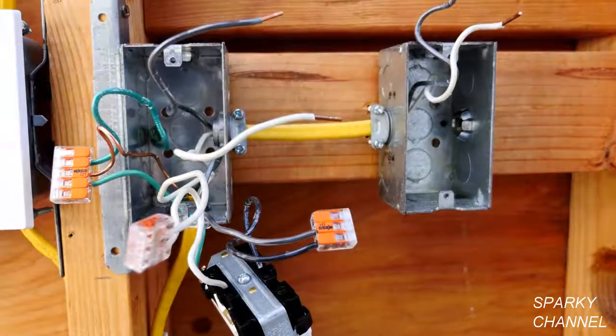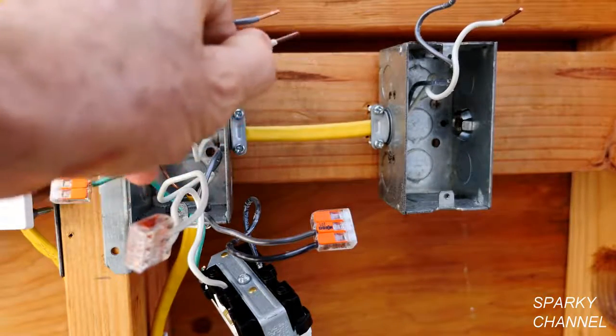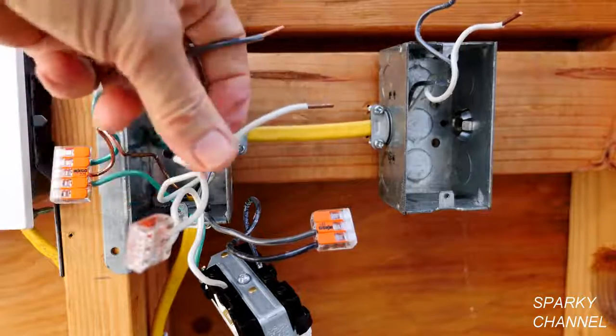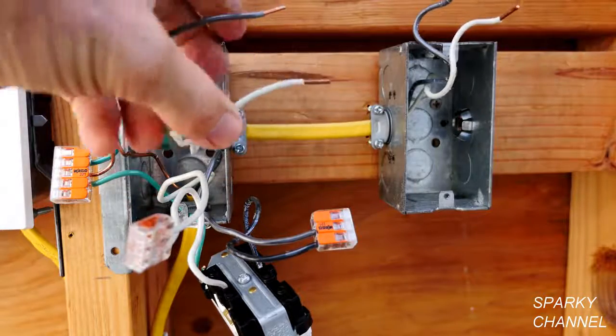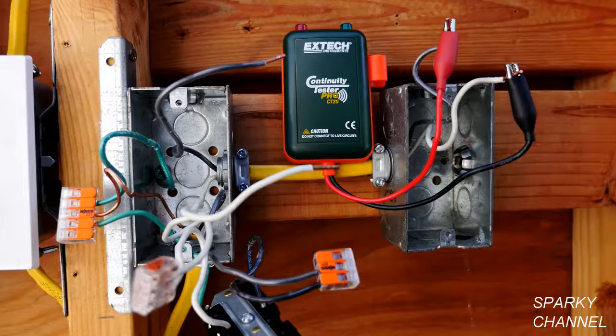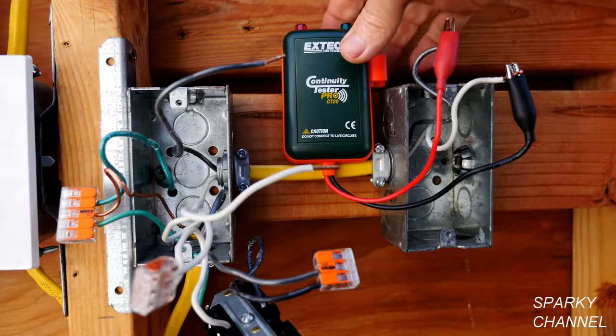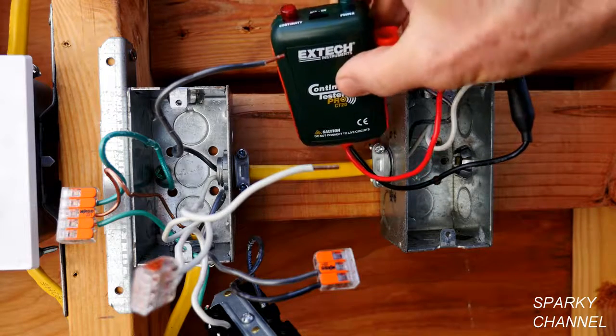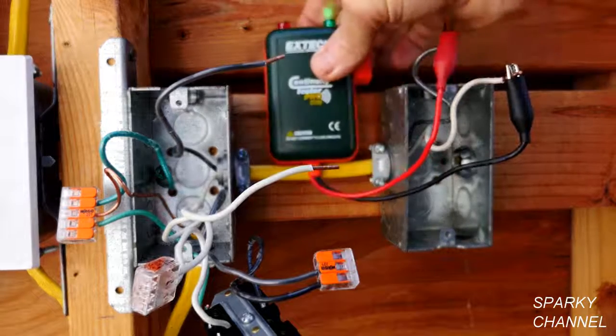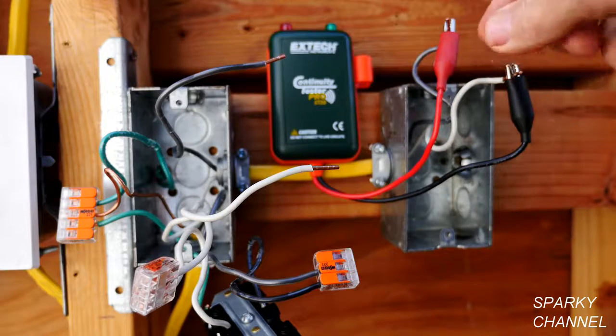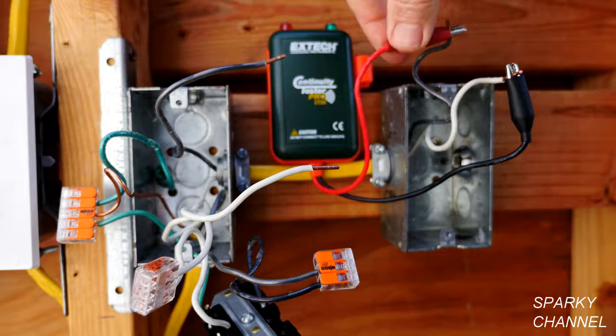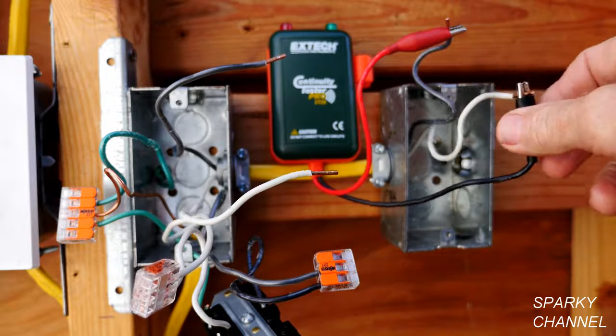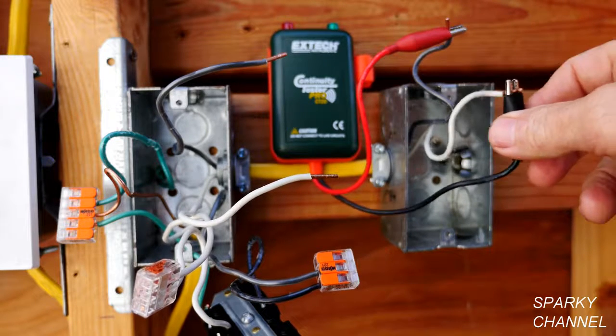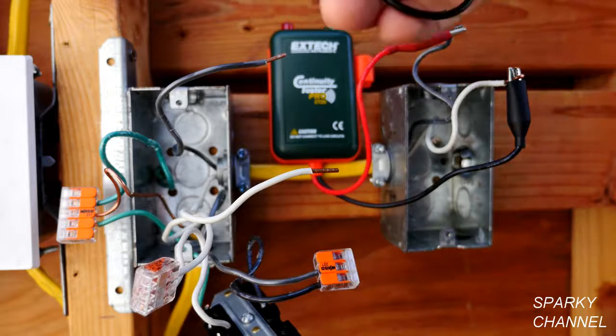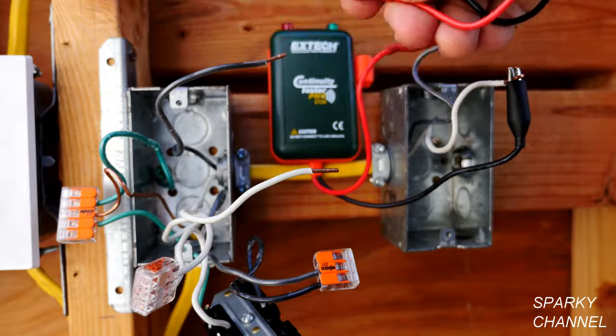Perhaps these receptacles would be in a bedroom and they're maybe 5 feet apart, something like that. So you suspect that they might be continuous, but you have to check to make sure. This is my Extech wireless continuity tester. And so I'm going to turn it on. And you see I have the red lead connected to the black hot wire and the black lead connected to the white neutral wire. And then this is the wireless component to the tester.